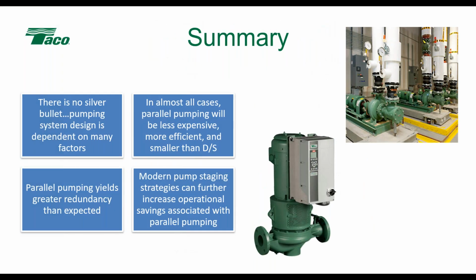So to sum all this up, as much as I'd love there to be a silver bullet, pumping system design is dependent on lots and lots of different factors, and we as engineers have to take all that into consideration. That's where having a manufacturer like Taco that you can rely on is a godsend, because we can run all these different scenarios and figure out what makes the most sense. In almost every case that I've ever looked at, parallel pumping has ended up being less expensive, more efficient, and has a smaller footprint than duty standby, because the pumps are going to get smaller.